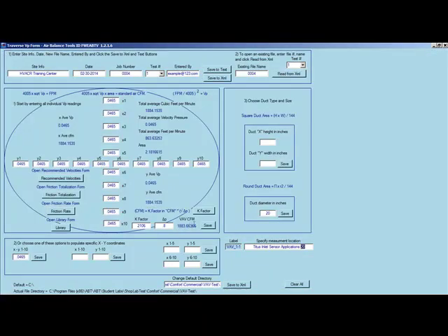1883 CFM moving across this box would have a change in pressure as it goes through the box. That change in pressure downstream is going to be a reading velocity pressure of 0.0465, which would actually equate to 1884 CFM based on a feet per minute change, obviously, as there is a pressure drop and an area change.